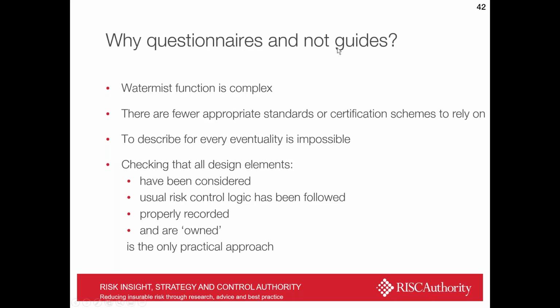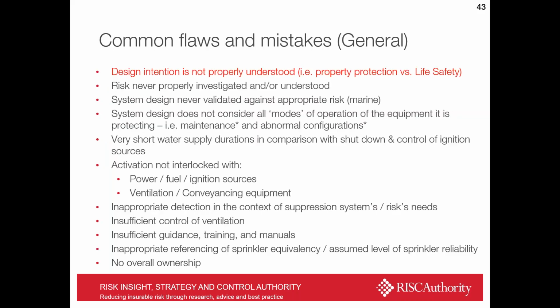Why have we done questionnaires and not produced guides or installation rules? Well, Watermist function is complex, as you've seen, and there are fewer standards than there are for sprinklers to rely on for their installation. And really, I hope you've seen the science is quite complex here, and to describe for every eventuality is almost impossible. But what the questionnaires do is check that all the design elements have been considered, that the usual risk control logic has been followed, properly recorded, and is owned by someone. And we felt that was the only practical approach to go to.